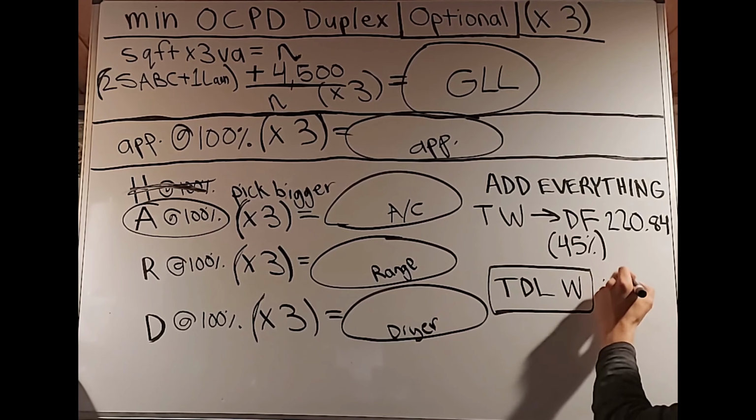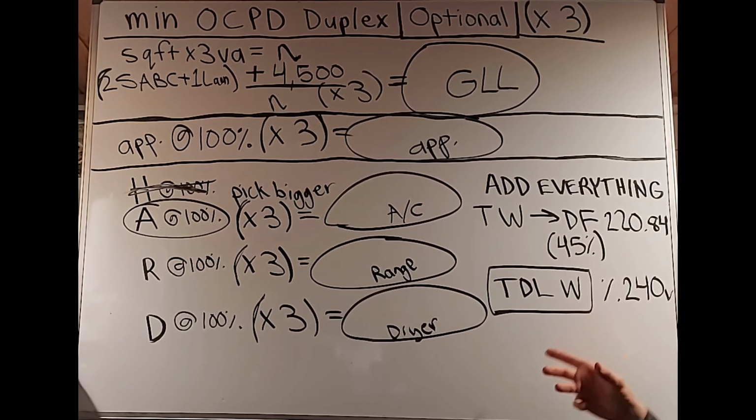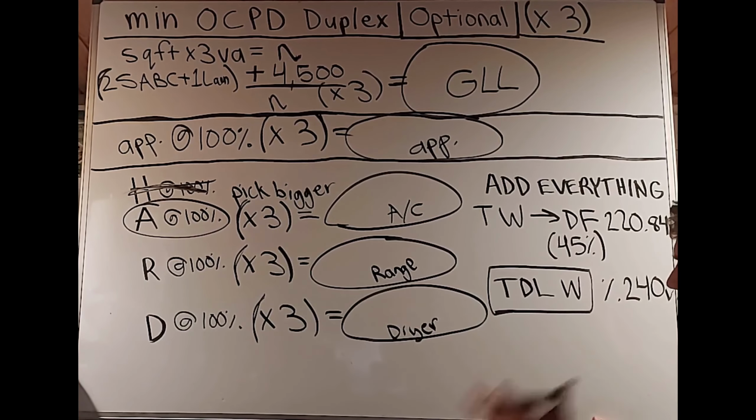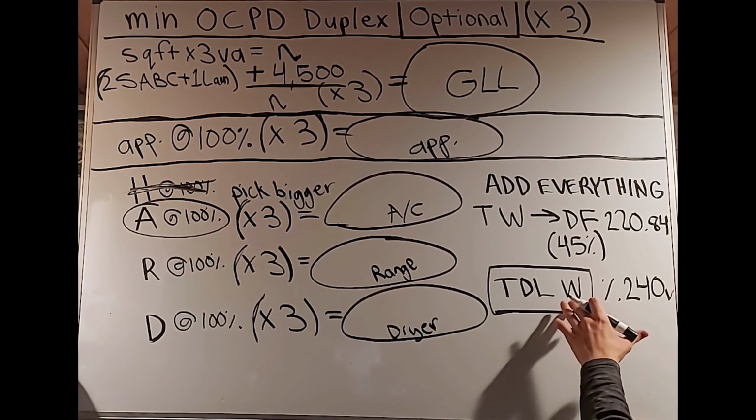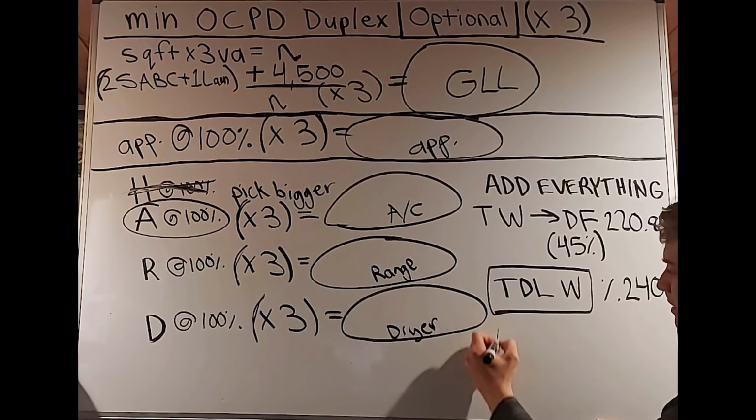And we're going to want to divide this by 240 volts from here. This is because watts is also going to be thought of as volt amps here in the load calculations, because we're not thinking about power factors or anything. So we're not thinking about efficiency ratios or anything. We're just thinking about the plain numbers. So we could think about this as volt amps. So we're going to divide by our volts, and that's going to give us our amps.